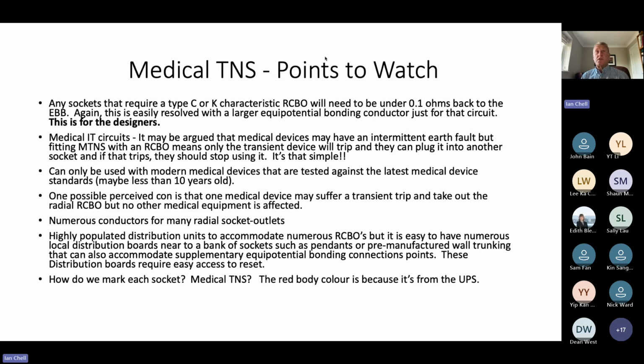So what do we need to watch with medical TNS? You need to look at the supplementary equipotential bonding values. That's up to designers. And I was alerted that it may need to be under 0.1. It depends on the circuitry, but watch out for time delay earthing requirements, okay? So it may be argued that medical devices may have an intermittent earth fault, but fitting MTNS with an RCBO means that the transient device will trip and they can plug it into another socket, and if that trips, they stop using it. It's that simple.